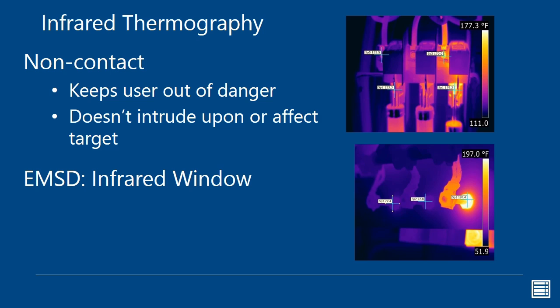A very important point here is that most visual viewing windows that incorporate glass or plastics do not allow infrared energy to pass through. So although you can visually look through them, the infrared camera can't. So you will require an infrared window that has a specialized lens that enables a camera to look inside.